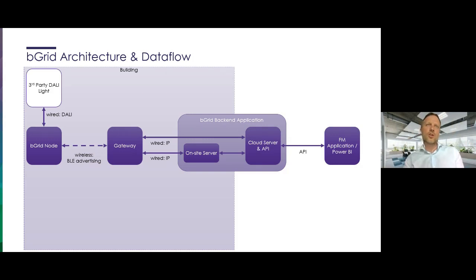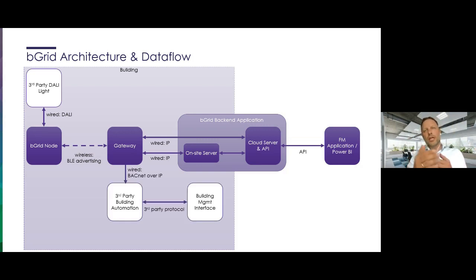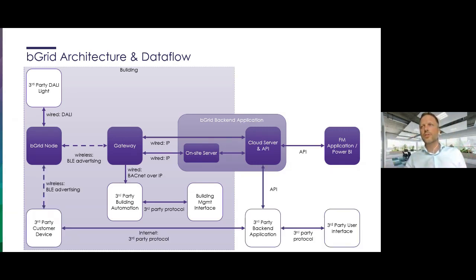We connect our nodes wired with a 2-core DALI cable to light fixtures, so we can control any brand of fixtures as long as they have DALI, or we put a DALI relay in between. We connect to the BMS through BACnet over IP on the same IP cable going to our gateway, sharing all our sensor data and any alterations to the set points of the climate or blinds.